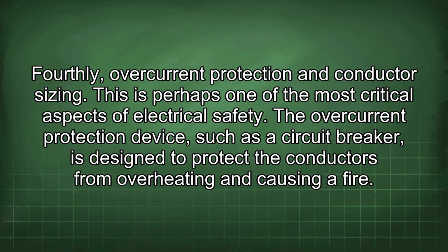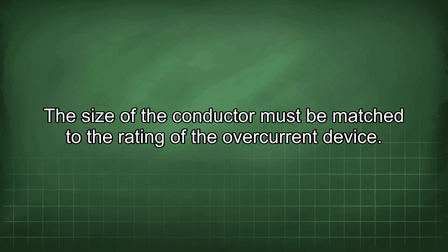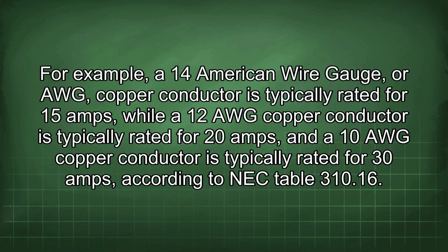Fourthly, overcurrent protection and conductor sizing. This is perhaps one of the most critical aspects of electrical safety. The overcurrent protection device, such as a circuit breaker, is designed to protect the conductors from overheating and causing a fire. The size of the conductor must be matched to the rating of the overcurrent device. For example, a 14 American Wire Gauge, or AWG, copper conductor is typically rated for 15 amps, while a 12 AWG copper conductor is typically rated for 20 amps, and a 10 AWG copper conductor is typically rated for 30 amps, according to NEC Table 310.16.